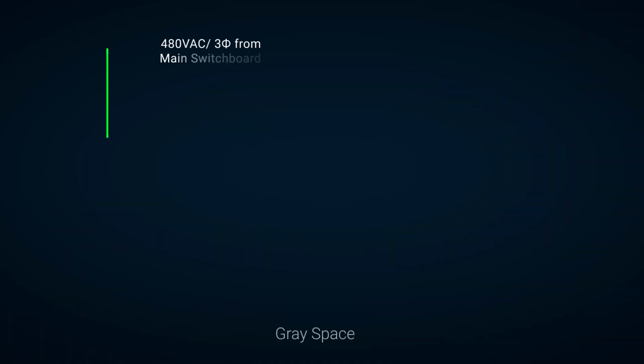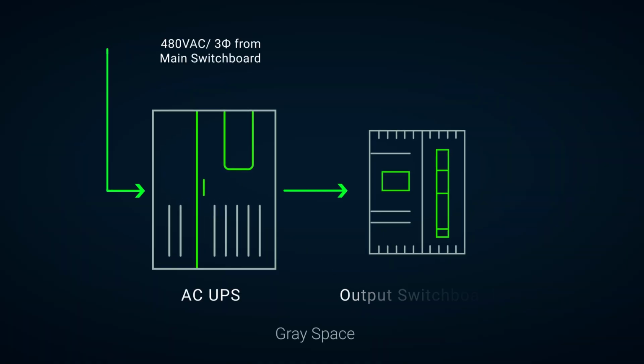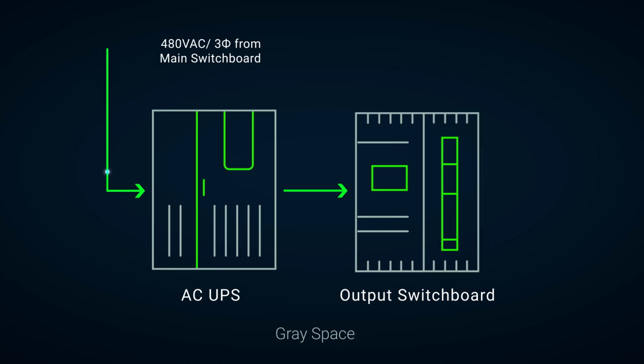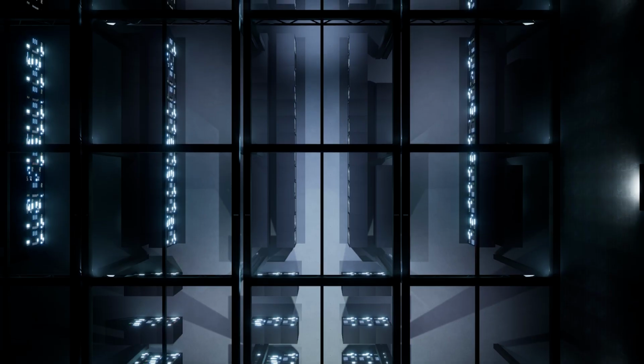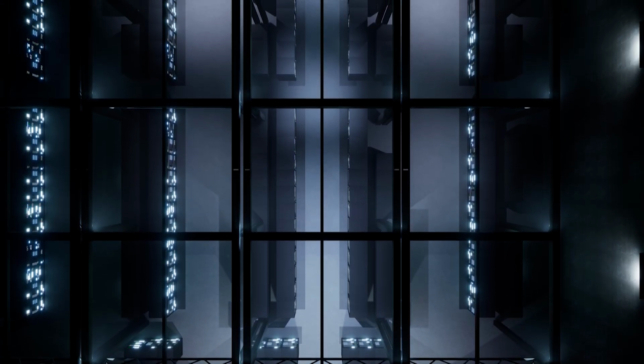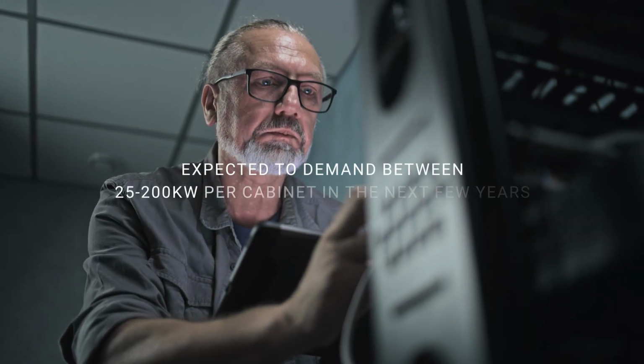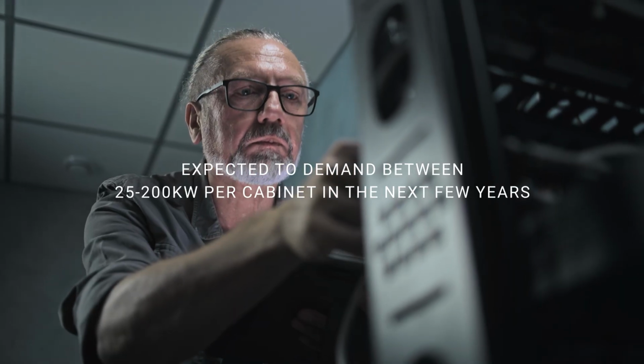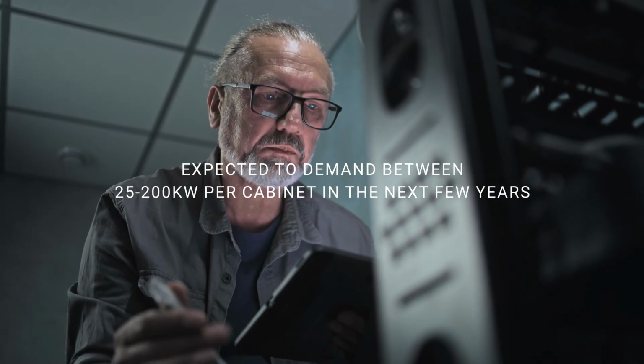Current power infrastructure in data centers typically supports between 3 kilowatts and 14 kilowatts per cabinet, primarily using 415-volt AC three-phase power. But that's not nearly enough power to support AI workloads, which are expected to demand between 25 and 200 kilowatts per cabinet in the next few years. This presents significant challenges for traditional power infrastructure.